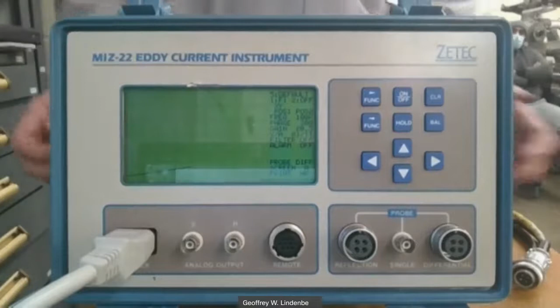We've got our phase. Phase sets the angle that primarily our liftoff, or that all our indications occurs in. So right now that's set to 300 degrees, but the actual setting there is you're going to set that based on how your display comes out.